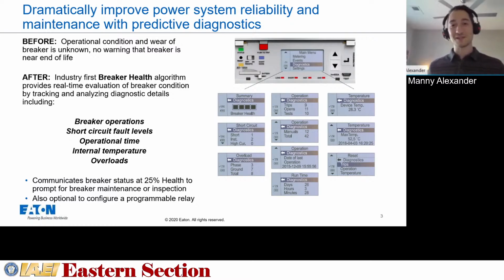So that's a very simplistic way and a very simple analogy to breaker health, but it essentially does the same thing, right? It gives you the ability to monitor the health of your overcurrent protective devices within your panelboard or switchboard assembly to avoid that unplanned downtime, or maybe you want to get a replacement breaker on the shelf so that when something does happen to that breaker, if it takes that hit, that next fault that maybe puts the breaker at end of life, you're prepared to quickly get your operations back up and running.